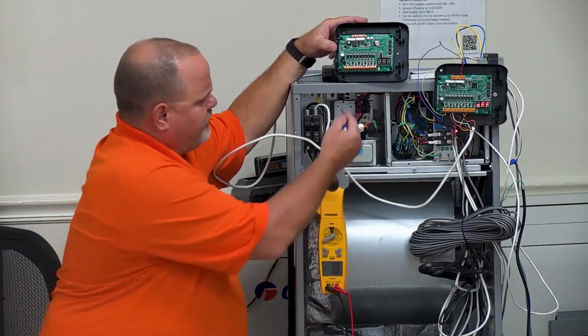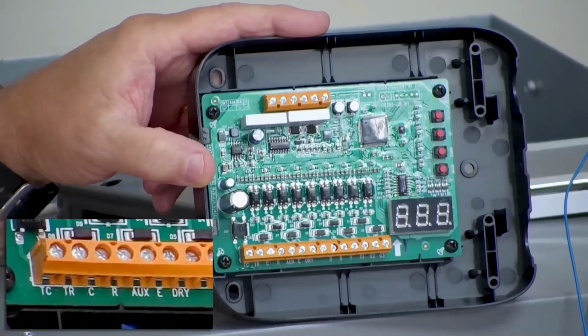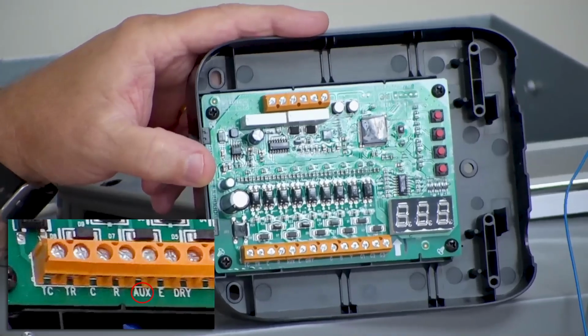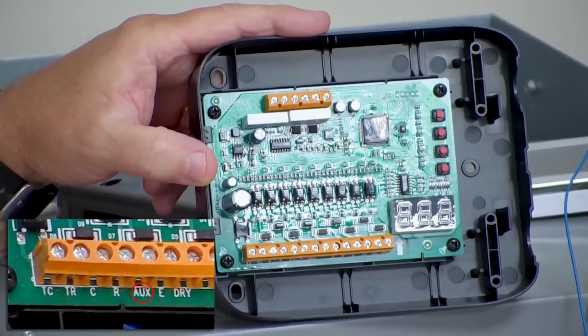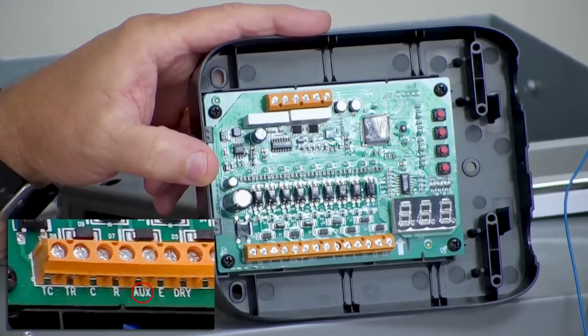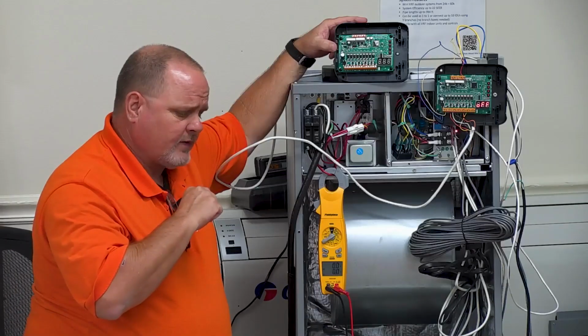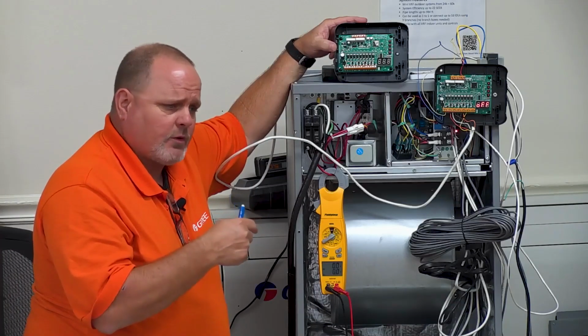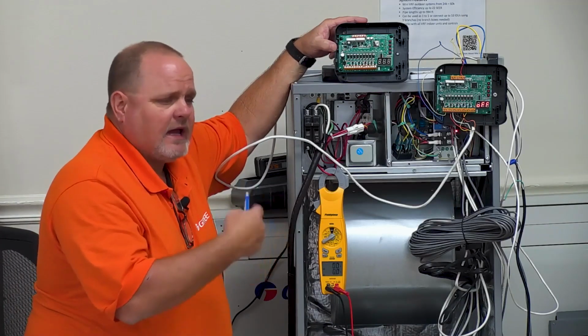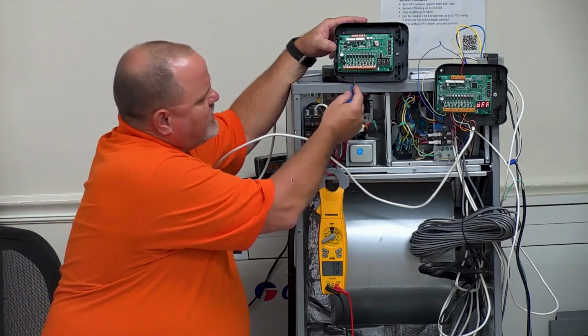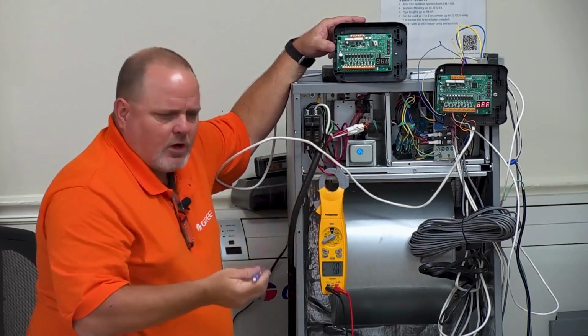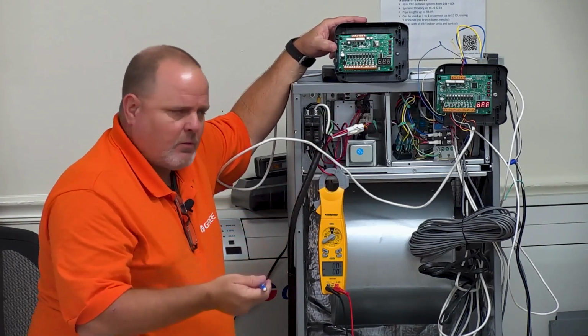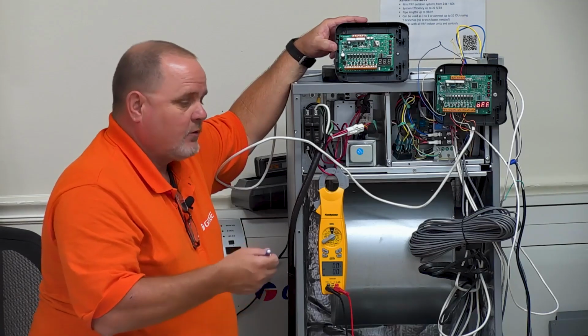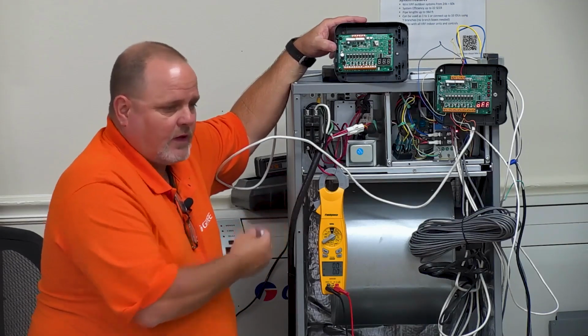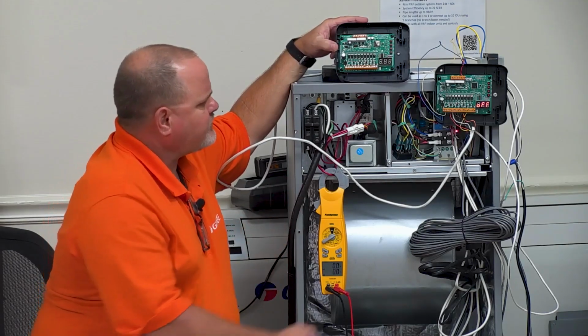So the auxiliary is exactly that. When you get a Y call, the heat pump's running. For whatever reason, the heat pump is not keeping up, and you get the auxiliary heat call on top of it, where we're running the heat pump and the electric heat. That's when auxiliary comes in. So that would be your W2 or auxiliary, depending on what kind of thermostat you have. When you get a signal to that, that will turn on the electric heat and the air handler.